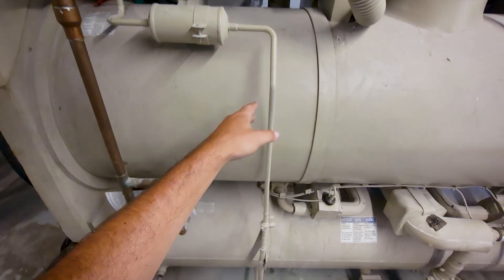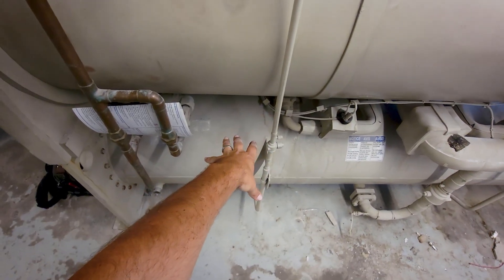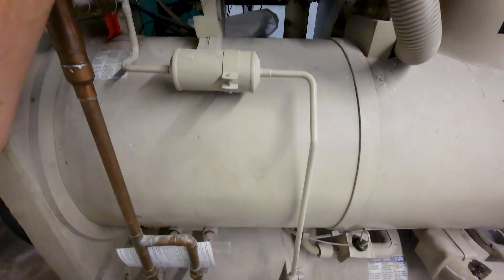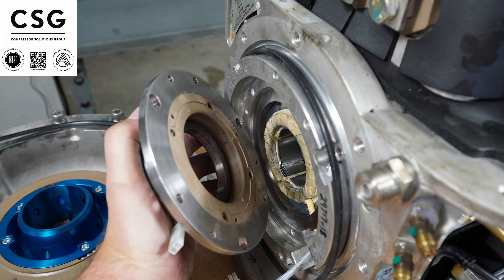Instead of typically trying to compete directly with Turbocor, it's easier to work with them and use their compressor, then use their own in-house compressor on larger machines. Once we break over four or five hundred tons, you'll see the in-house mag bearing compressors being used — things like the YMC² or YZ by York, or a WME by Daikin. These are just some examples; everybody's got their own.